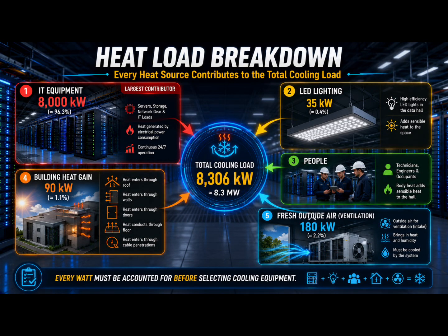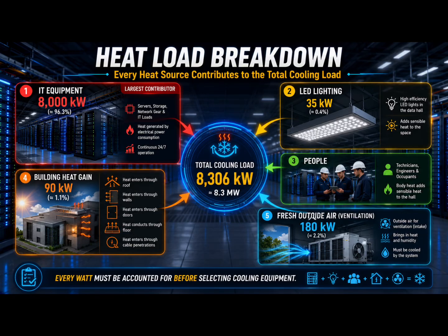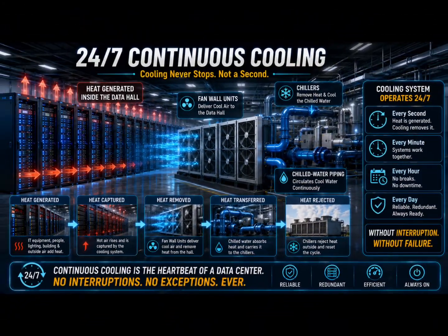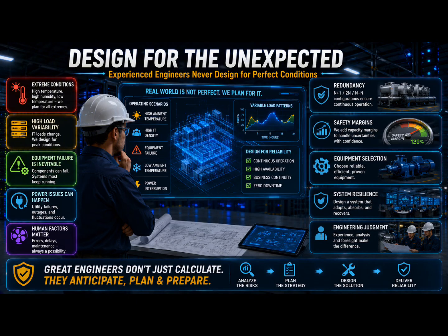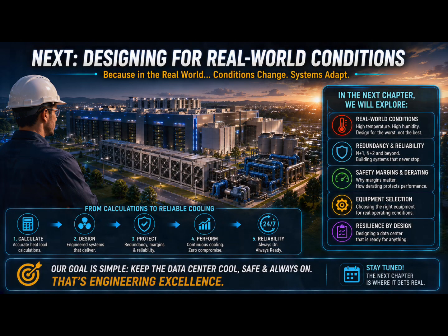Now let's calculate our total cooling load. IT equipment, 8,000 kilowatts. Lighting, 35 kilowatts. People, 1 kilowatt. Building heat gain, 90 kilowatts. Fresh outside air, 180 kilowatts. Add them together, and the result is 8,306 kilowatts, or approximately 8.3 megawatts. That is the actual amount of heat our cooling system must continuously remove. Every second, every minute, every hour, without interruption. But are we ready to select our cooling equipment? Not yet, because experienced engineers never design for perfect conditions. And that's exactly what we'll explore in the next chapter.